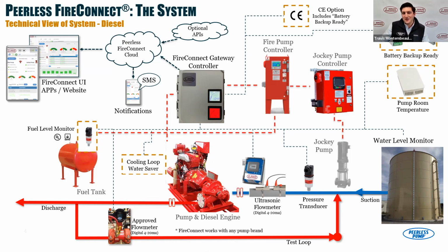Now, those only tell you so much information, but within these fire pump controllers, in electrics there are at least 70 plus pieces of data that we can gather, and in diesels there are 40 plus pieces of data. Each of those items would typically reflect as a common trouble or system trouble alarm in your building. So the impact is I get a phone call at 2 a.m. and I'm the fire site leader, and somebody says, "Hey boss, I've got a system trouble alarm in the fire pump room.